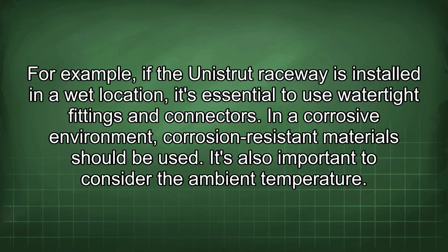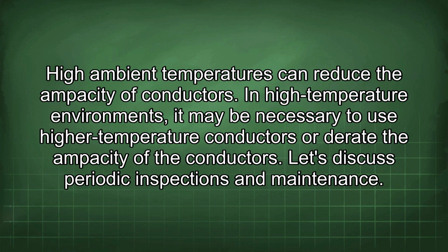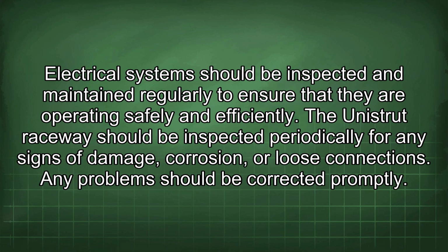For example, if the Unistrut Raceway is installed in a wet location, it's essential to use watertight fittings and connectors. In a corrosive environment, corrosion-resistant material should be used. It's also important to consider the ambient temperature. High ambient temperatures can reduce the ampacity of conductors. In high-temperature environments, it may be necessary to use high-temperature conductors or lower the ampacity of the conductors. Let's discuss periodic inspections and maintenance. Electrical systems should be inspected and maintained regularly to ensure that they are operating safely and efficiently.